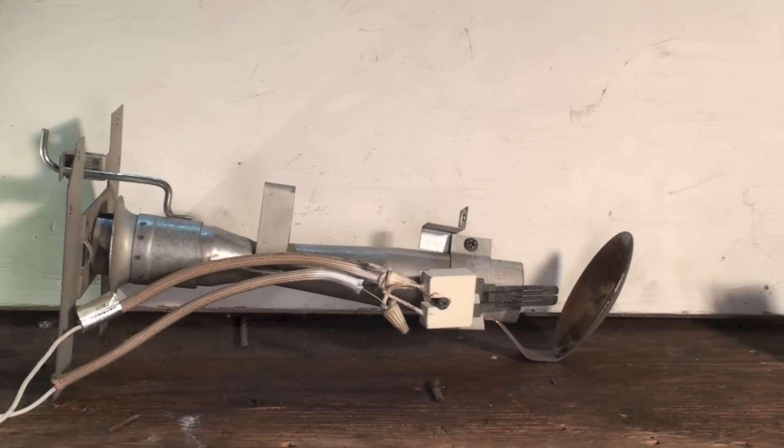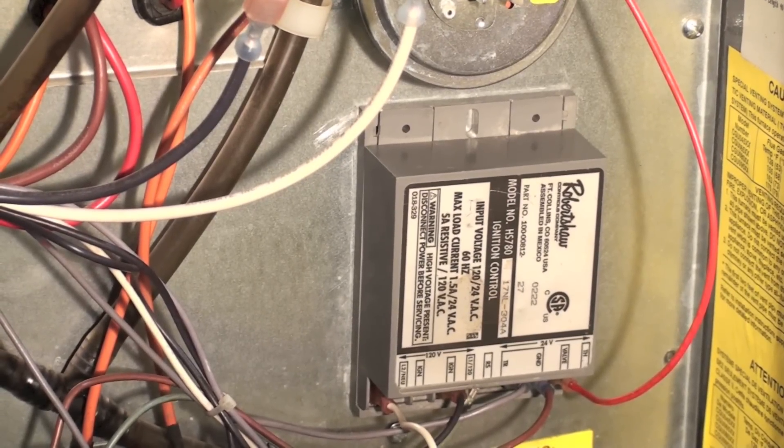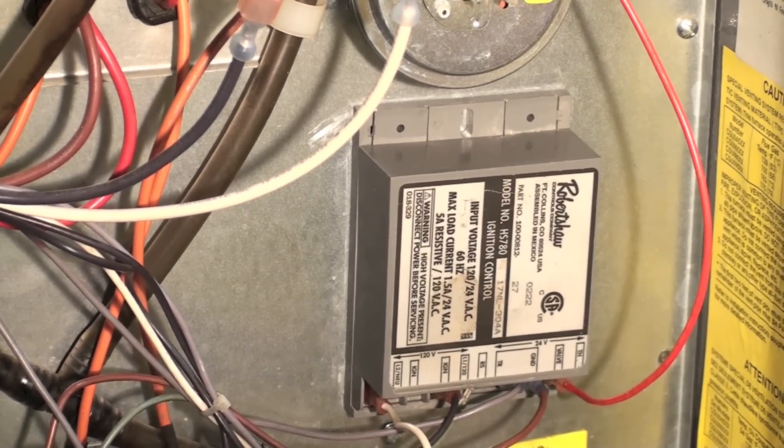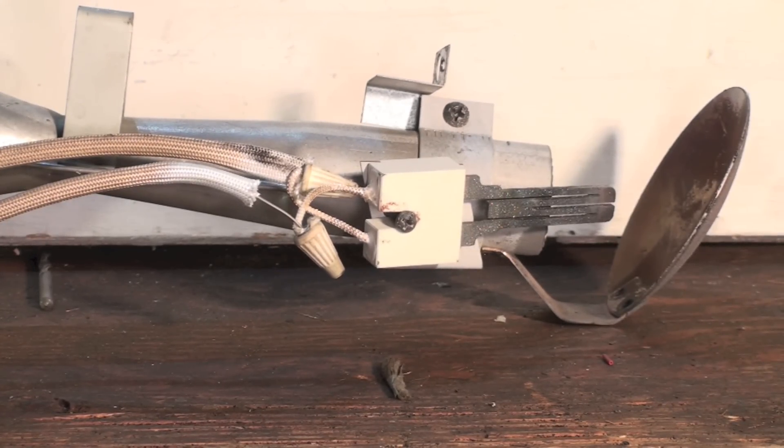The Robertshaw HS 780 control that we have on this thing. There's that control there. That's that Robertshaw HS 780. It was not set up for a flame rod.